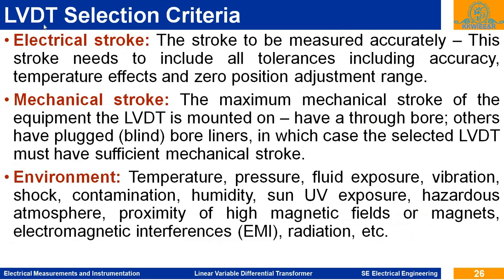Now, how to select the LVDT? There are some criteria. First, electrical stroke. The stroke to be measured accurately. This stroke needs to include all tolerances, including accuracy, temperature effect and zero position adjustment. So we have to define these parameters.